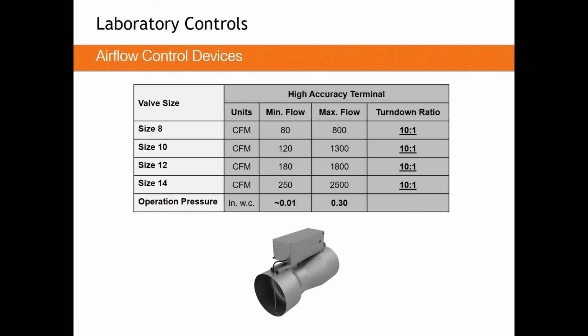Now, if you call and say, hey, we have a 1/10 of an inch available, can we use a high accuracy terminal? The answer is yes, but you will not get the full turn down. If you have a 1/10 of an inch on a size 8, you might get 100 or 200 or 300 CFM, but you just can't get that full turn down ratio. That's an important point to remember with a high accuracy terminal. We sometimes call these low pressure Venturi valves. That's not a term I personally like to use because it's a little bit misleading. Yes, these can operate at lower pressure drops, but it comes with a caveat of you won't get the full turn down ratio.